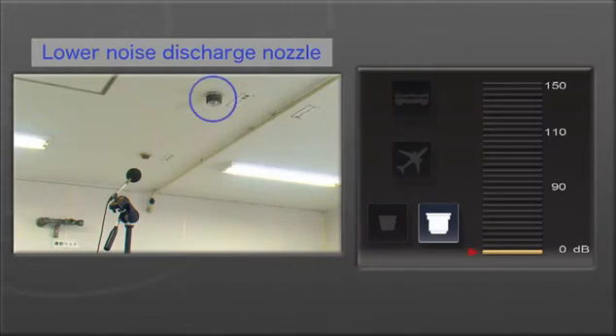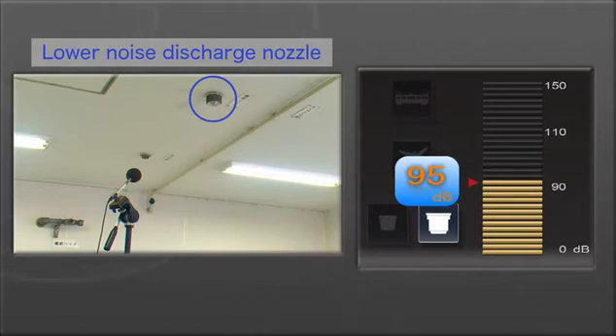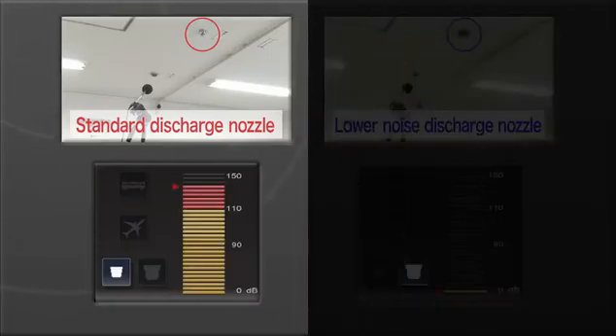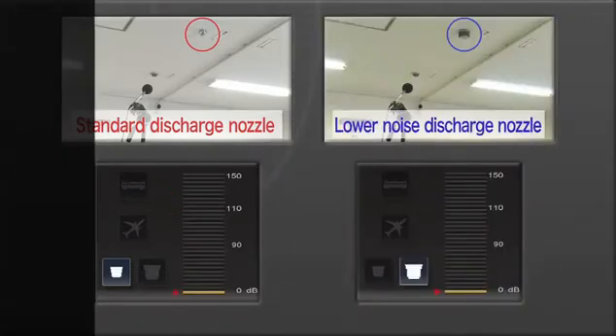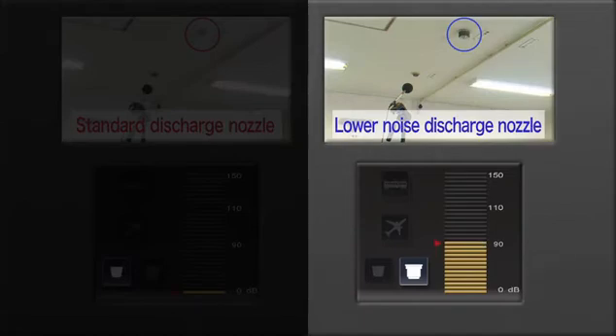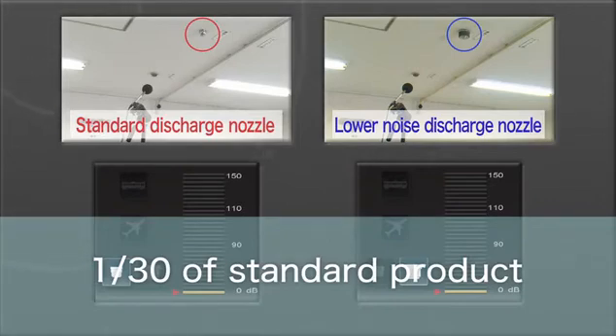Now, let's take a look at an experiment using our newly developed lower noise discharge nozzle. The results show noise at a decibel level in the 90s, achieving a major reduction of 30 decibels or more. This value corresponds to roughly 1/30th the noise of standard nozzles in terms of perceived loudness. As you can see, the effects on hard disks are minimized through a major reduction in the gas discharge noise when compared to a standard discharge nozzle.